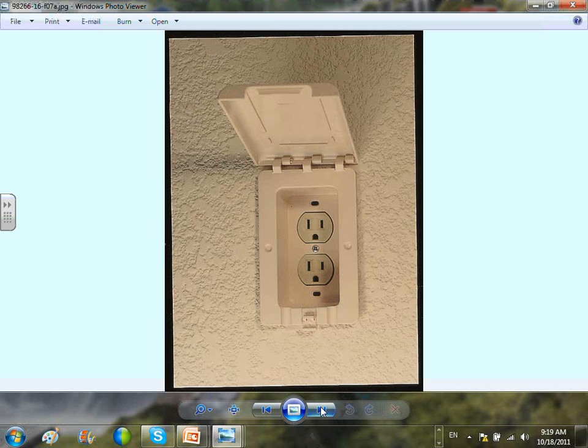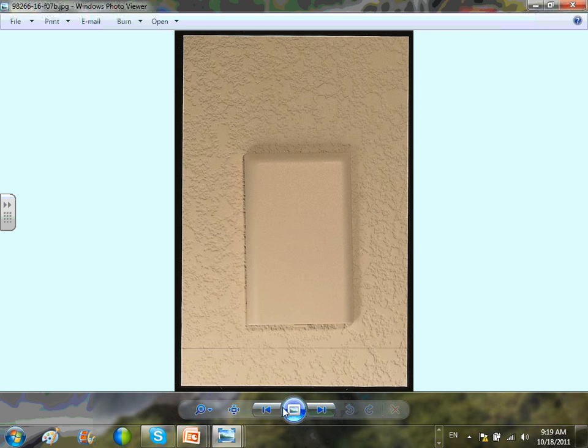For receptacles, guys, you need to have an in-use cover. This doesn't look like an in-use cover unless it's inside. Yeah, it's pushed in. It is an in-use cover. Can you guys see what an in-use cover is? You push each one of them, and then you can cover it because it's a wet location. That bubble. This one is not a bubble because the receptacle is set back. That's actually nicer than a bubble, don't you think so? Yes, sir.